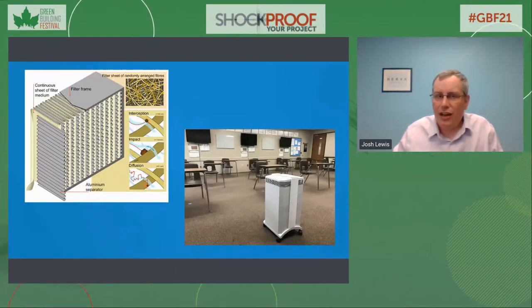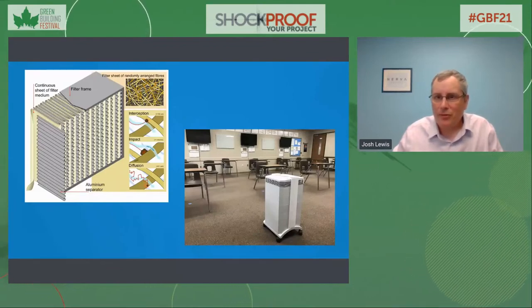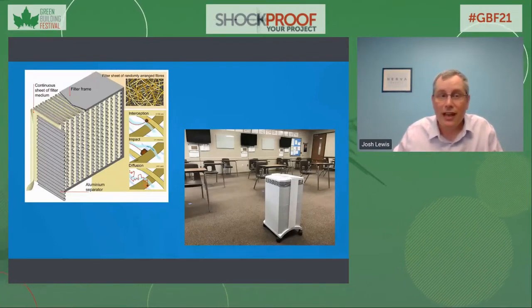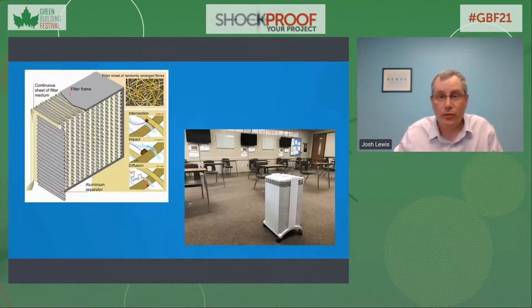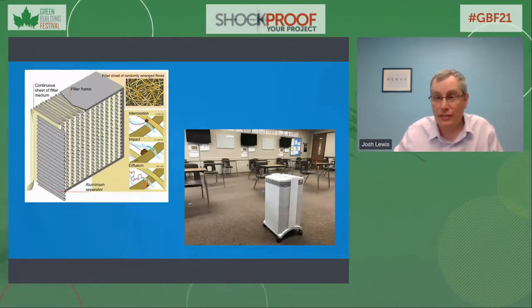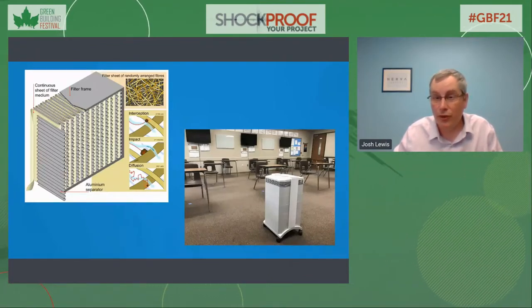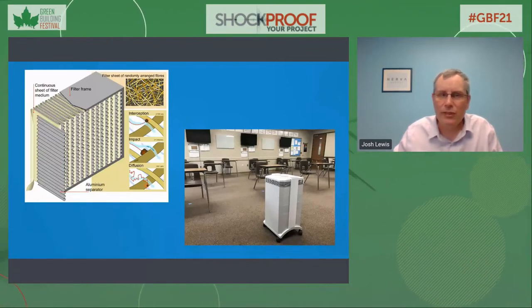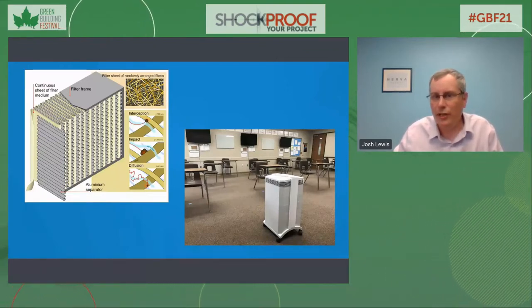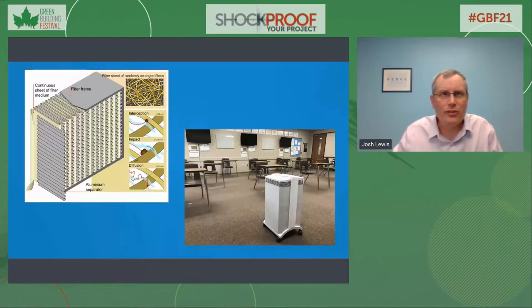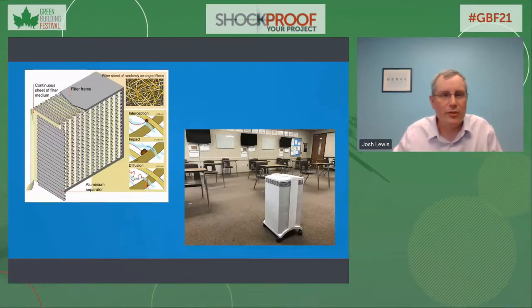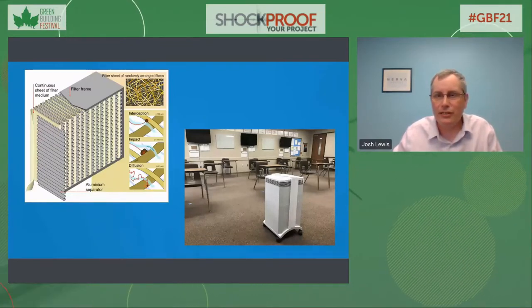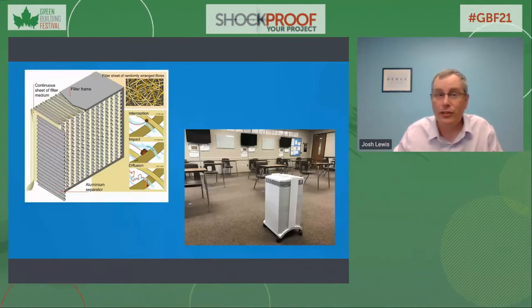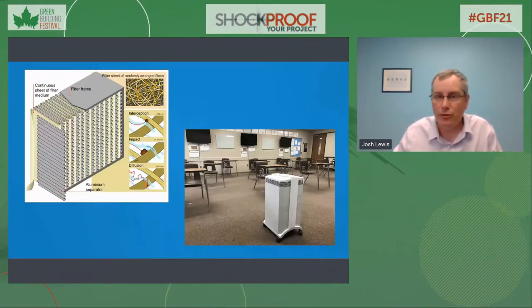There has been a lot of talk since the pandemic started about HEPA filters. HEPA, also known as high efficiency particulate absorbing filter or high efficiency particulate arrestance filter, depending on where you're from, have equivalent MERV ratings between 17 to 20. Now, this type of filter has typically been used in healthcare facilities and other buildings that are very sensitive to indoor air quality, including laboratories and manufacturing facilities with clean rooms.